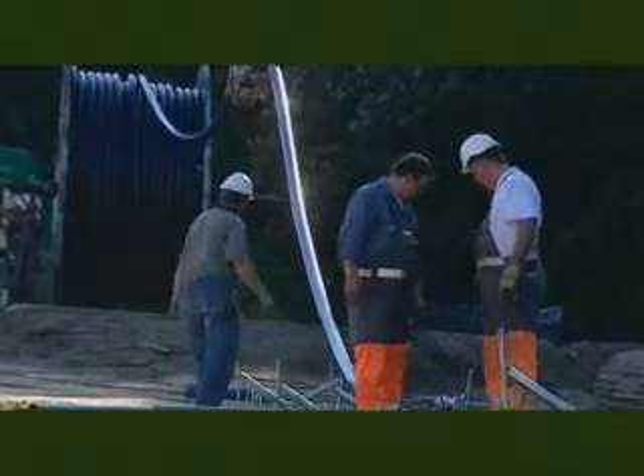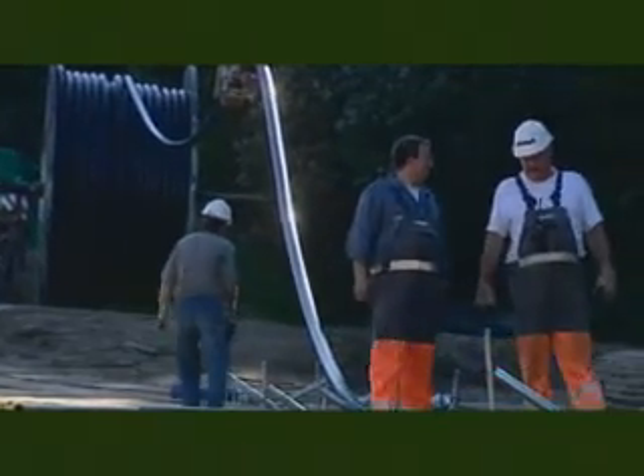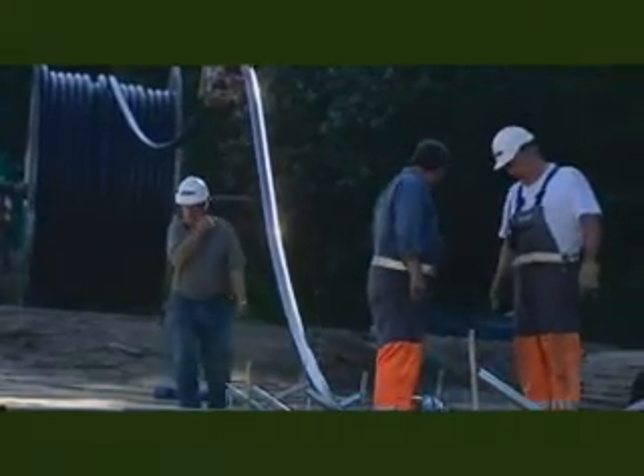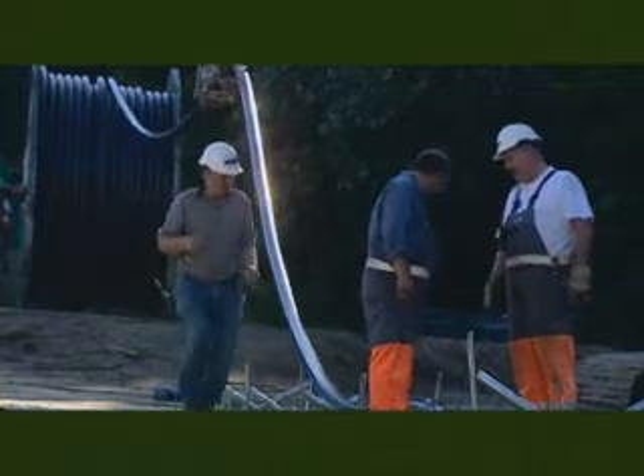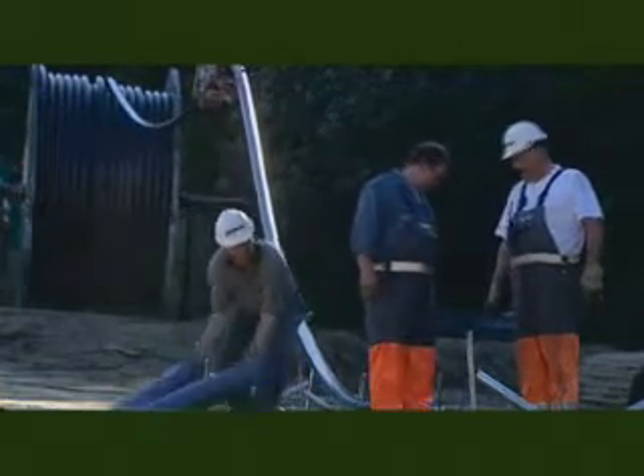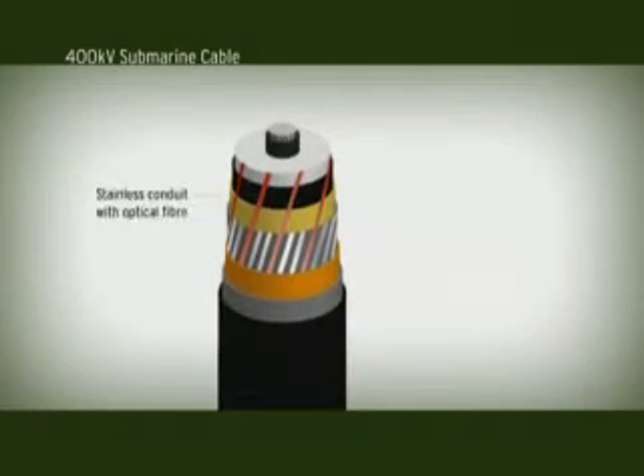The submarine cable is equipped with a thick 5mm sheath because the cables are being pulled over such a long distance through the pipes. The submarine cables have built-in fibre optic cables in the cable shield. This avoids the need to draw separate fibre optic cables across the inlet. Each cable has 6 times 4 fibres. For each circuit, this adds up to 72 fibres.